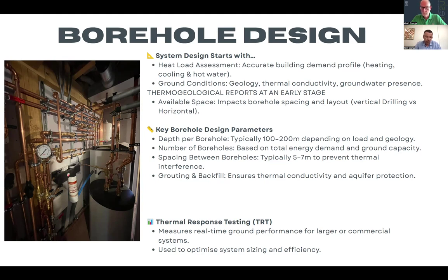So we could do this first, and the borehole which is used for the thermal response test can be used for the future number of boreholes, so that can be included in the later design of the system. To do the design of the system, we need a full heat loss assessment, so an accurate building demand profile for heating, cooling, hot water. We then assess the ground conditions, geology, thermal conductivity, groundwater presence, and any other reports that we've got available.